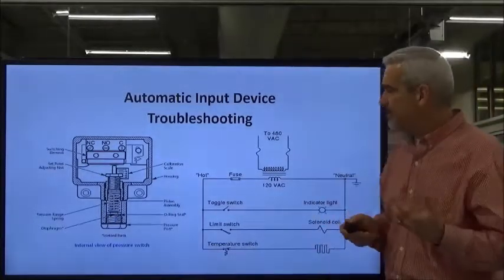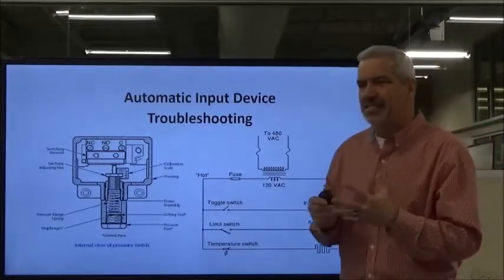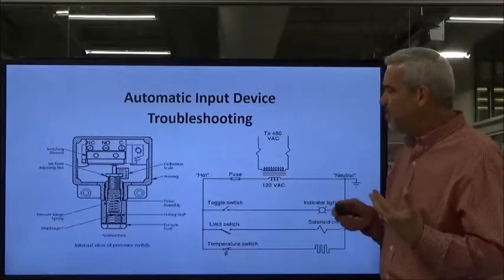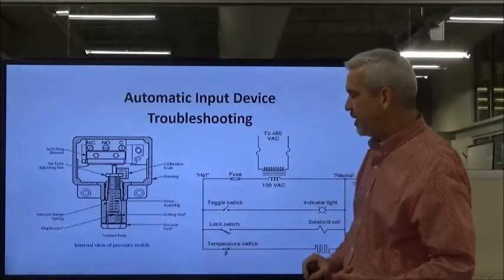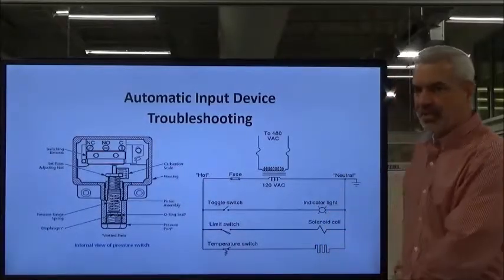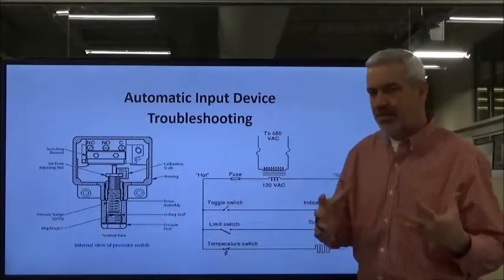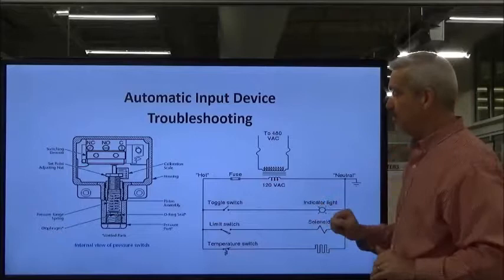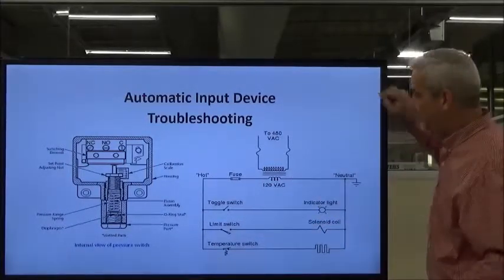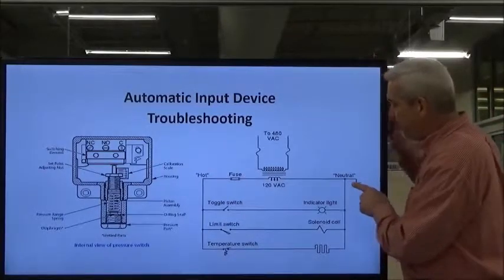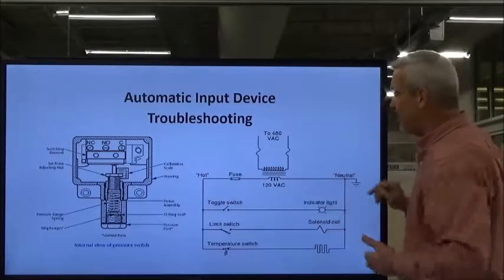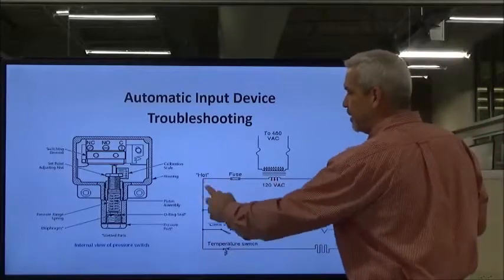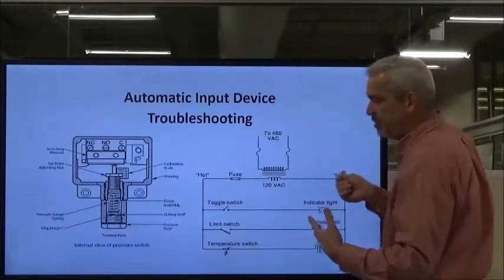I want to talk to you just a little bit about some of the troubleshooting for these devices. It's a little difficult to do troubleshooting lessons with the video. You have to really get your hands on it. So I just want to talk to you a little bit. I see a lot of you trying to measure voltage across the switch. Technically, yes, you can do that. But what I would like to see you do, until you get a little bit stronger, I want you to get your head around this. You've got power coming out of your transformer, and it's always trying to get back home. We stated that in 1401. So we always want to reference to neutral. Don't reference to ground because this may not be grounded. There are times where your transformer may not be grounded, so that's an erroneous reference point.